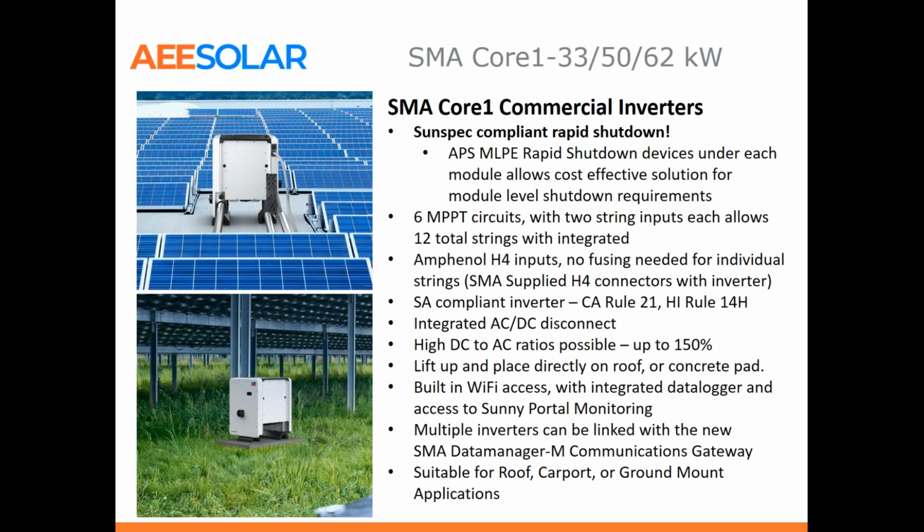Also note that all of these inverters that we're talking about are SA compliant, so they meet grid interactivity requirements to meet CA Rule 21 and Hawaii Rule 14H, so they all can be installed. This inverter is very nice as it comes with its own mounting feet. There's a nice little video on SMA that you can look at for the unboxing. It slides out of the box, you put the feet on, 2 little handles, put it in place either on a concrete pad or right on the roof. You can see examples of those mounting feet there in the photos.